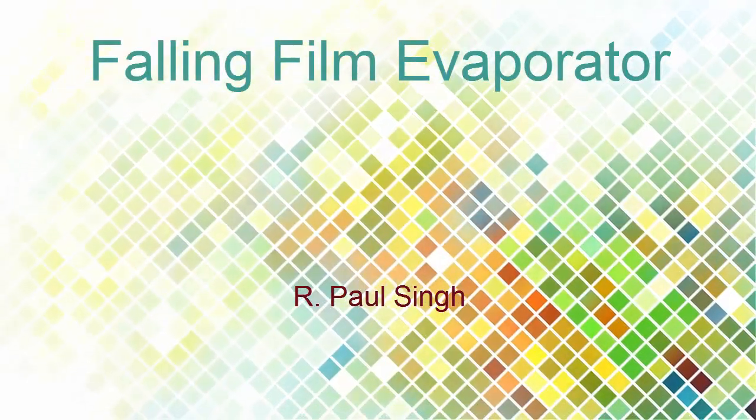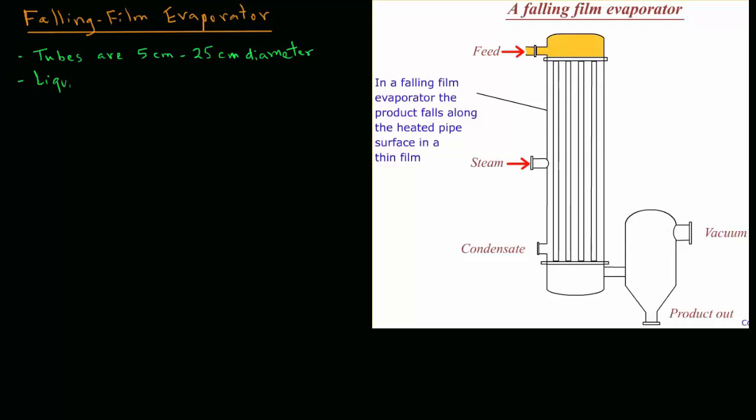In falling film evaporators, long tubes of diameters from 5 centimeters to 25 centimeters are used. The liquid feed enters from the top and the liquid flow inside the tubes is by gravity, but the design gets complicated to get a uniform distribution of the liquid as it flows down inside the tubes.